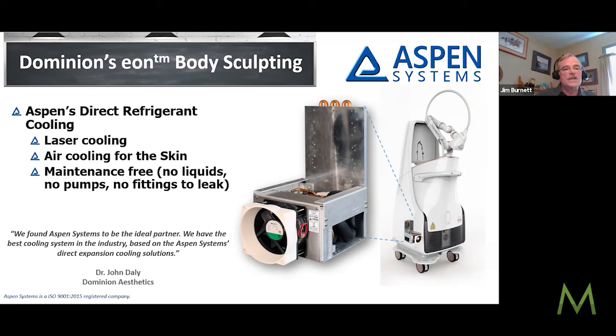Small, reliable, variable speed were all requirements, so we use a brushless DC motor, variable speed, highly compact. We run it up to 6,500 RPM, as low as 2,500 RPM, so we get a 3 times range in capacity out of one unit. Coupling that with an expansion valve allows the system to react to a wide range of conditions. We used an existing compressor design and put the motor technology together with it to run at high RPM to get the refrigerant displacement needed for high capacity.